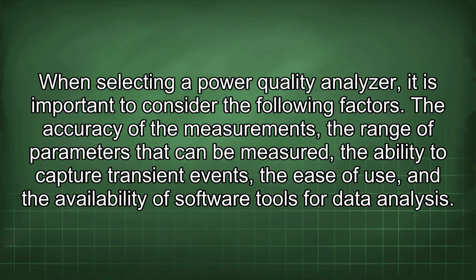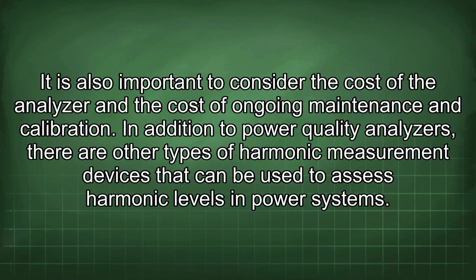When selecting a power quality analyzer, it is important to consider the following factors: the accuracy of the measurements, the range of parameters that can be measured, the ability to capture transient events, the ease of use, and the availability of software tools for data analysis. It is also important to consider the cost of the analyzer and the cost of ongoing maintenance and calibration.